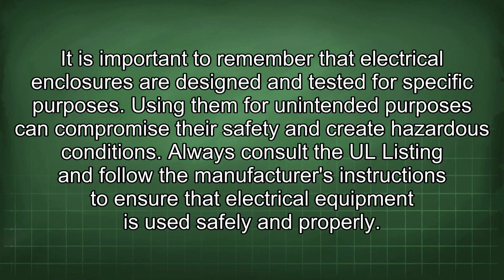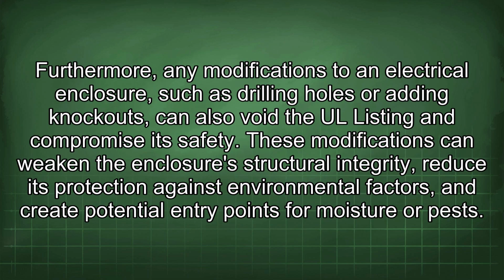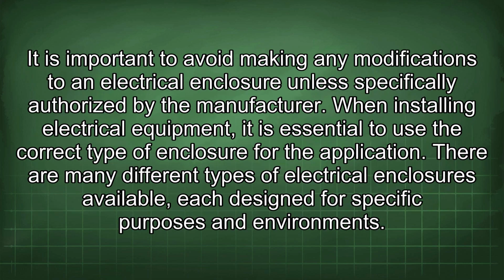Always consult the UL listing and follow the manufacturer's instructions to ensure that electrical equipment is used safely and properly. Furthermore, any modifications to an electrical enclosure, such as drilling holes or adding knockouts, can also void the UL listing and compromise its safety. These modifications can weaken the enclosure's structural integrity, reduce its protection against environmental factors, and create potential entry points for moisture or pests. It is important to avoid making any modifications to an electrical enclosure unless specifically authorized by the manufacturer.